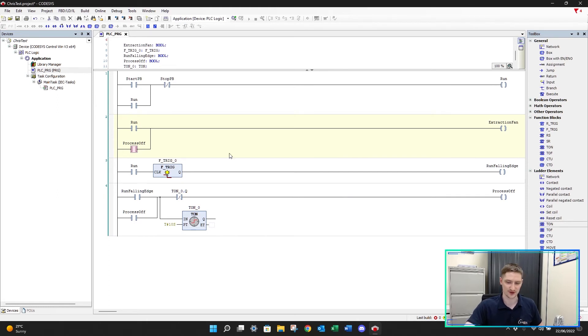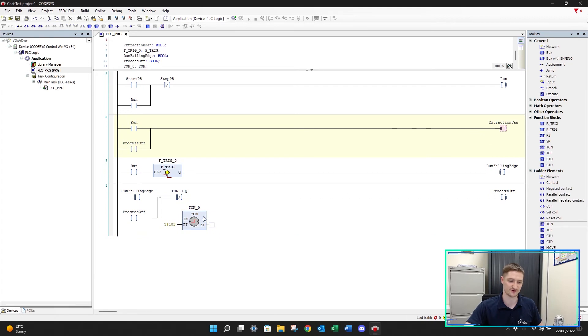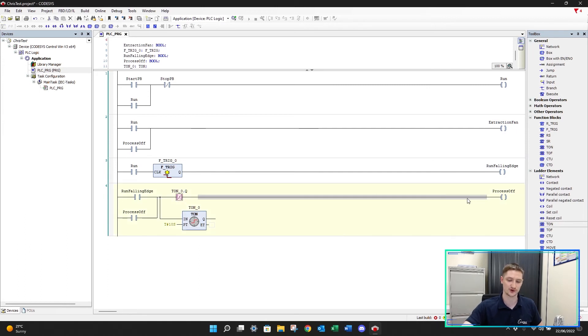Just to go over this once more: when our process is running, our extraction fan turns on. When the process turns off, the falling edge detects it and triggers 'run falling edge' for one PLC scan. We then latch on our 'process off' signal, which continues running our extraction fan. Meanwhile the on delay timer runs for 10 seconds, after which it resets our 'process off' signal, turning everything off.